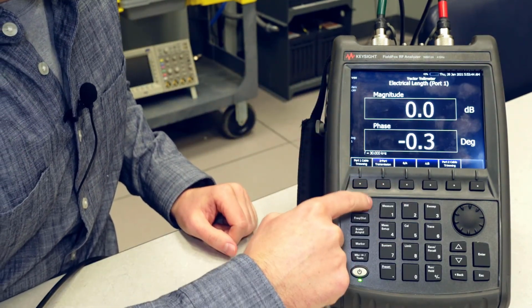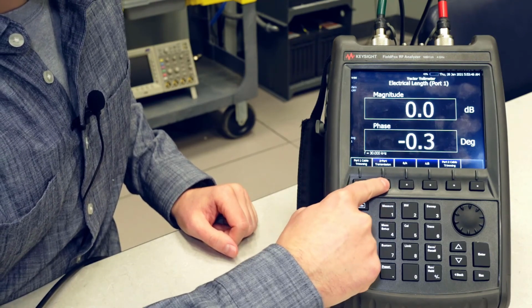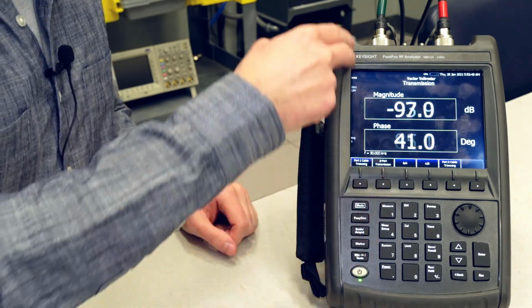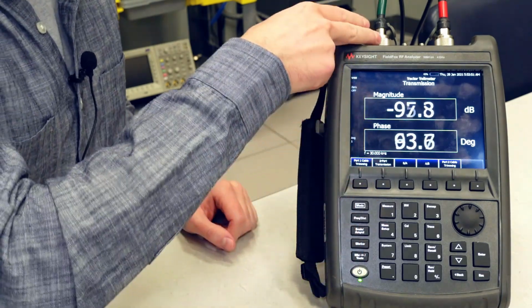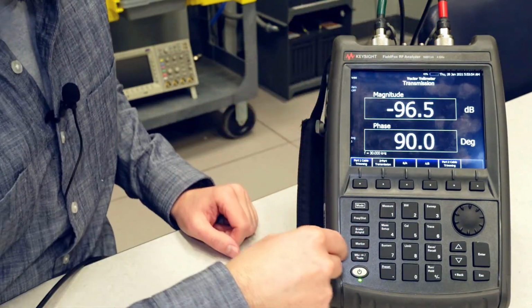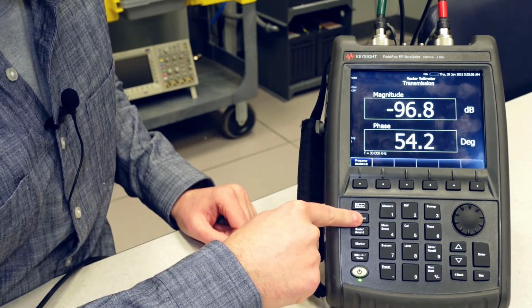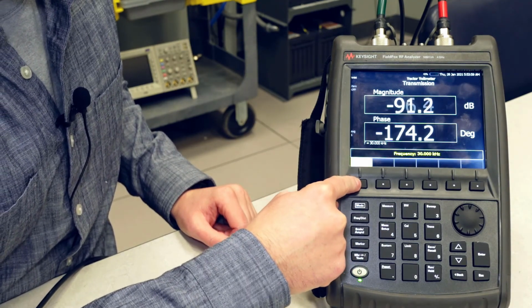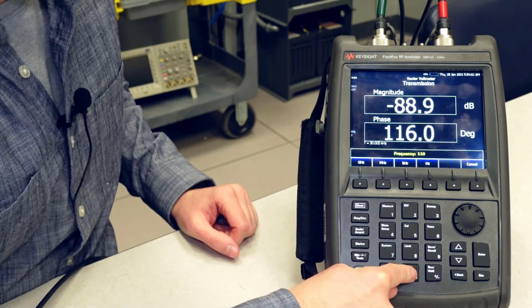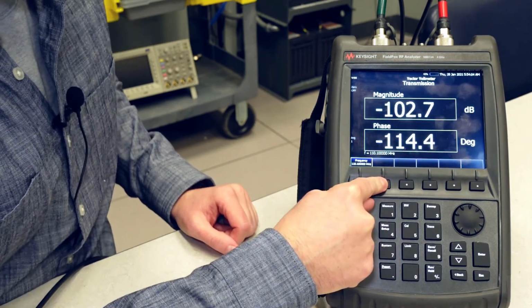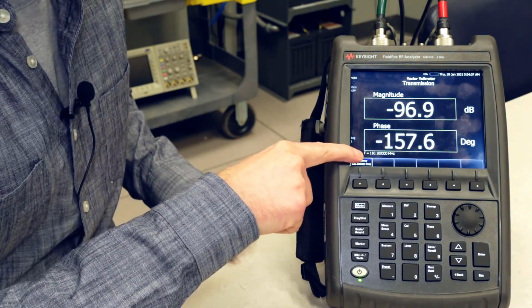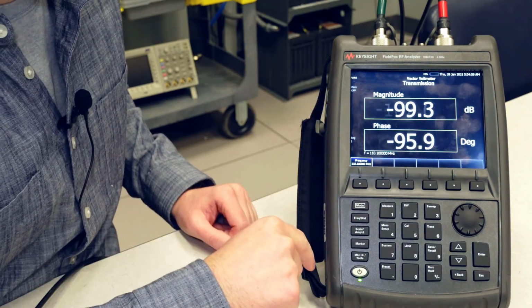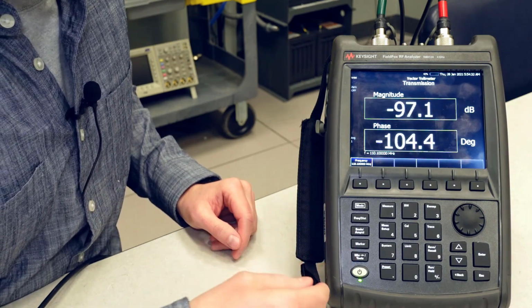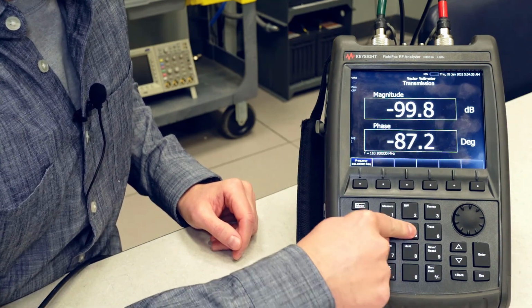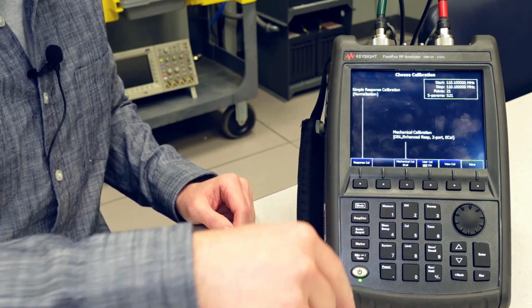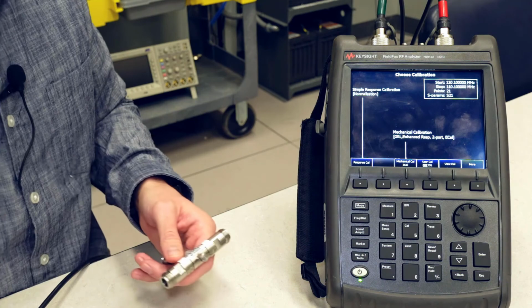We're going to start by selecting under measure 2 port. So this will utilize both ports, sending from port 1, receiving on port 2. And then we're going to hit the frequency key, and then frequency again, and we're going to set up 110 megahertz. And you can always verify that here under F equals, and then you can see the frequency there. Now we need to perform our calibration, which is the same process as the network analyzer mode. And I just hit cal, number 5, and I'll go through that process now.